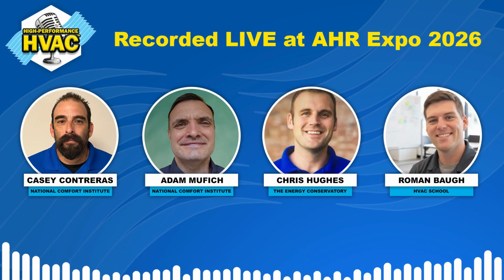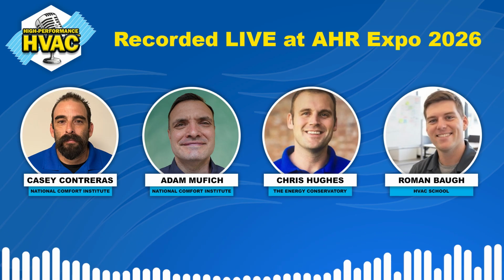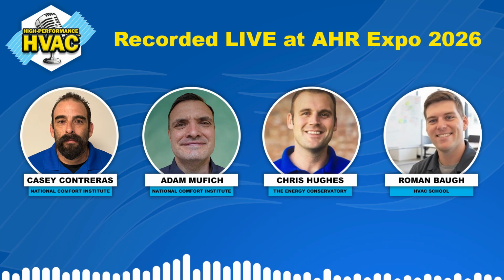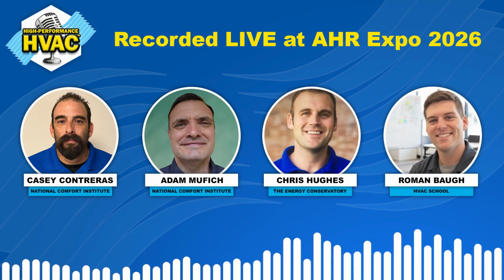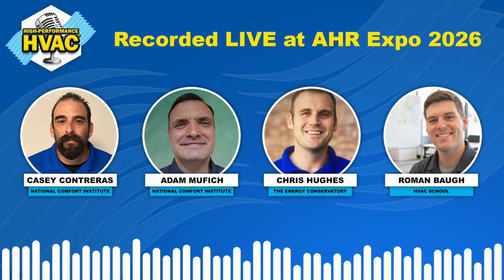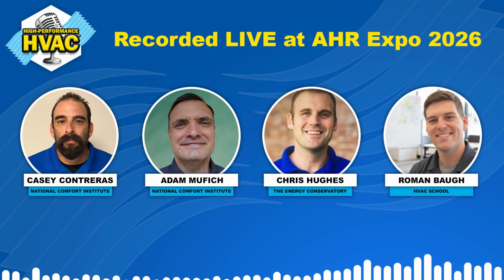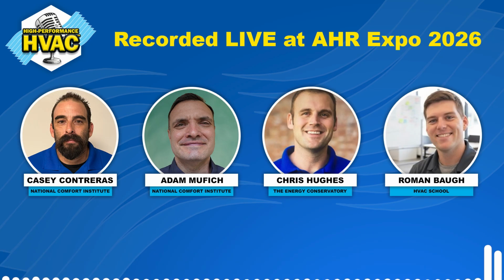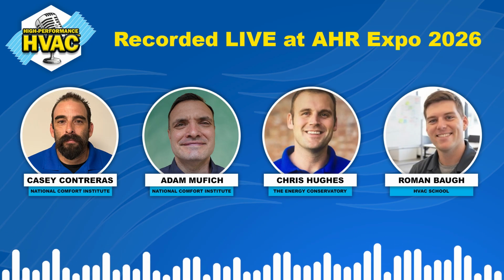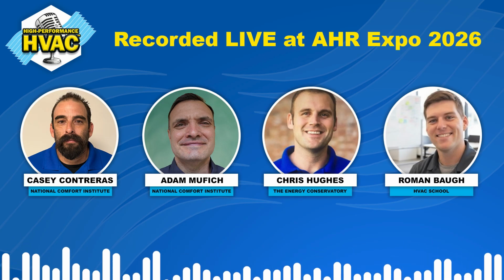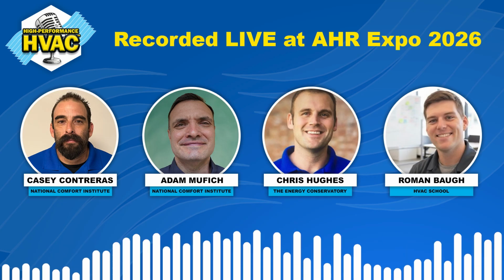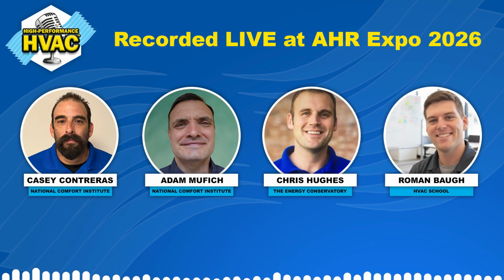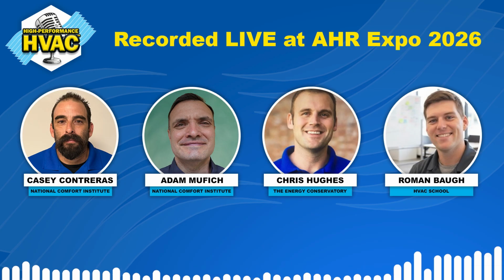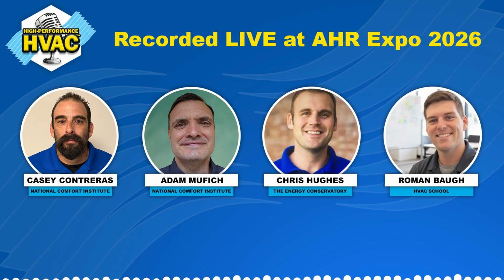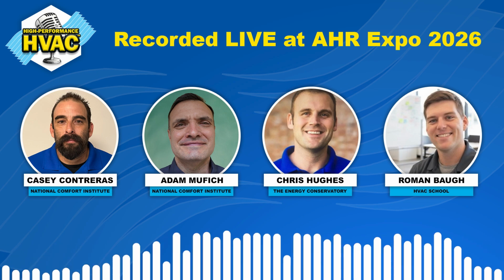If those are my reference points, it's going to be those spots in the system, but also the saturation temperature in those spots, because they're going to match, right? Leaving my expansion valve, maybe it flashed a little bit of gas, sure, but it's going to be within 2 degrees of my suction saturation temperature. It's at saturation. We know that to hold true. Discharge line, right? We know what my saturation temperature is there because of my pressure. We convert our discharge pressure to saturation temperature. That's going to be the hottest part. That's where we get discharge superheat from. If my suction line is 135, but my discharge line is 109, I physically can't have a 135 suction line. I physically can't have 135 anywhere in the system. Impossible. So when you're doing a thermistor check as your first initial thing, in my mind, how I think about this, I'd have the system off.